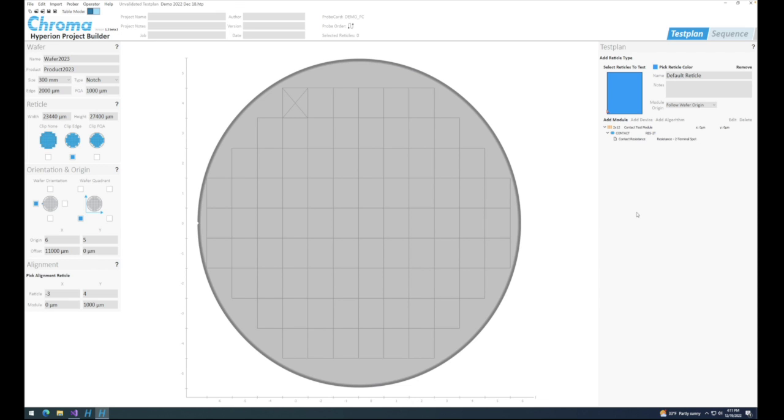To change or optimize parallel testing on the Chroma 3530: if certain tests must be executed before others, this is a dependency on the completion and execution order. If no such requirement exists, parallelization will execute as many algorithms not constrained by circuit topology as it can.